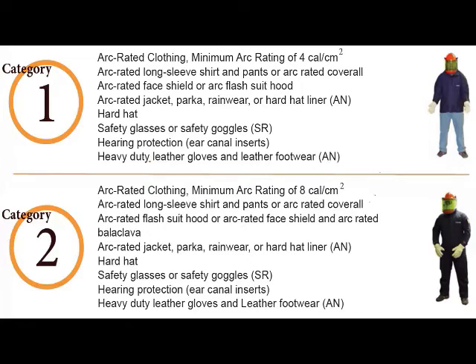Category 2 can be used at a rating of 8 calorie. Calorie is nothing but incident energy. Whenever an arc occurs, the intensity is measured in terms of calorie, meaning the heat, heat waves, temperature and pressure all put together, called calorie per centimeter square. So that is the 8 calorie.